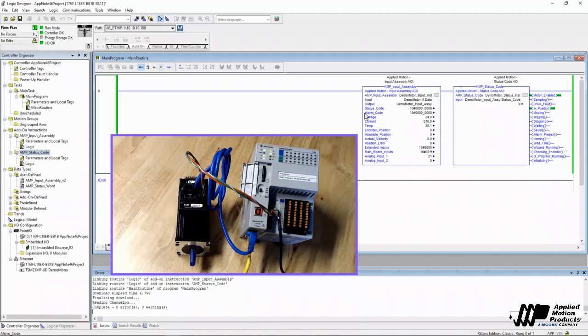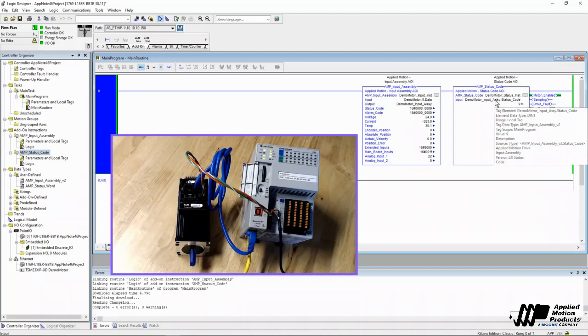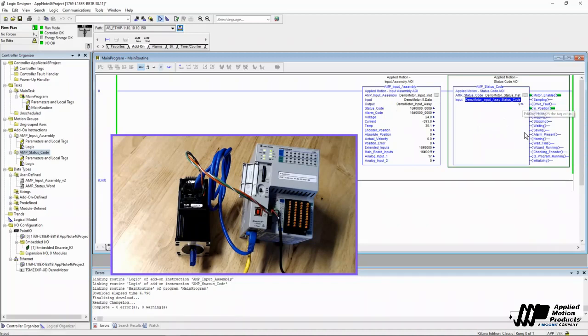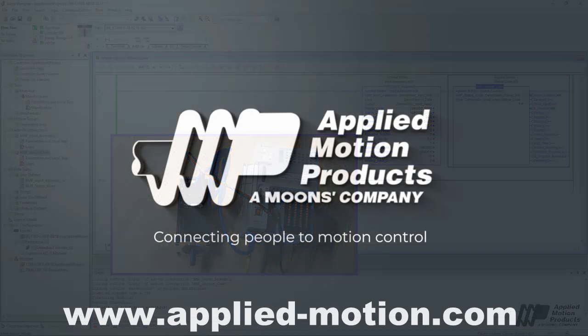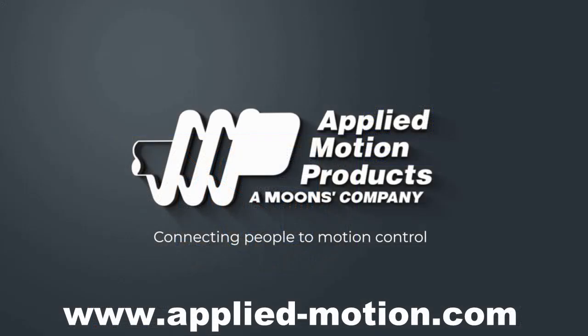And then you can see here we have a status code of 9, and that is in base hex, so base 16. What does that mean? Well, it's a little bit hard to say. That's why we have the status code AOI. So if we point this status code variable into the status code AOI, the status code AOI decodes it, and it tells us status code 9 means the motor is enabled and the drive is in position. Everything that we expect. And that's it.